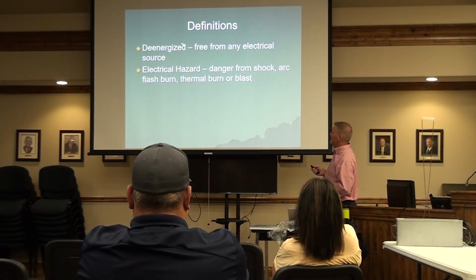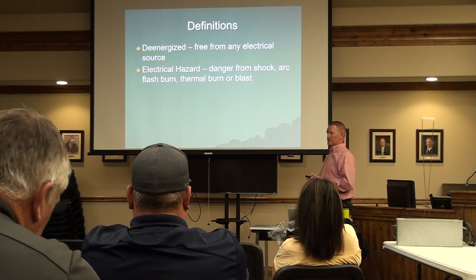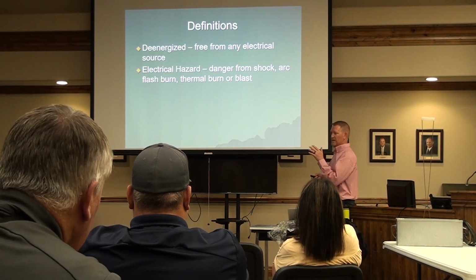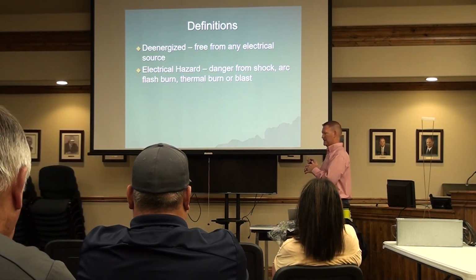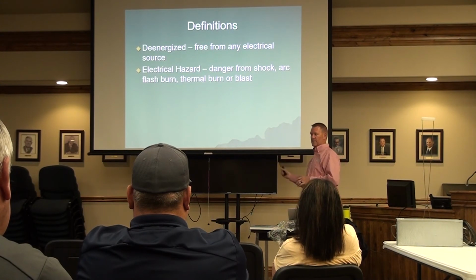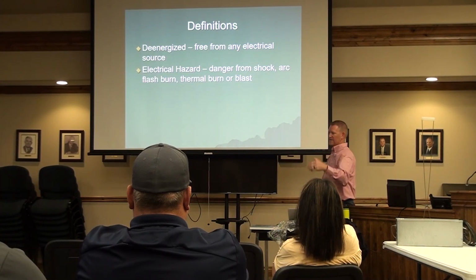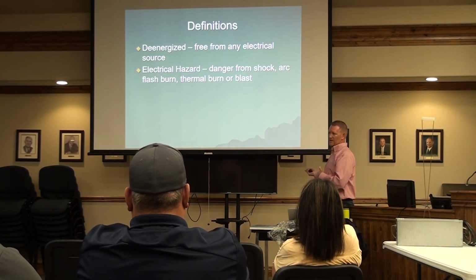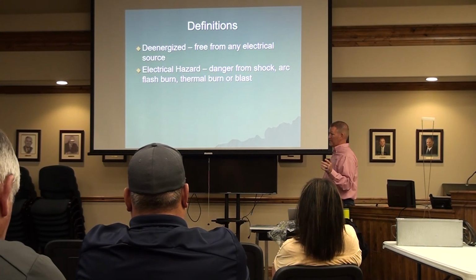De-energized - the one thing I'd say here is the only way you know anything's de-energized is if you throw a meter on it and make sure the meter is good beforehand. Go check that outlet - yep, there's 120. Go check that gear - yep, it's dead. There you go, now you know it's dead. Otherwise, you don't really know that meter's even working right. So I would get a good, reputable meter.